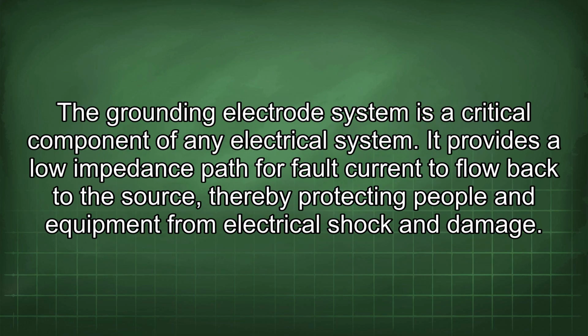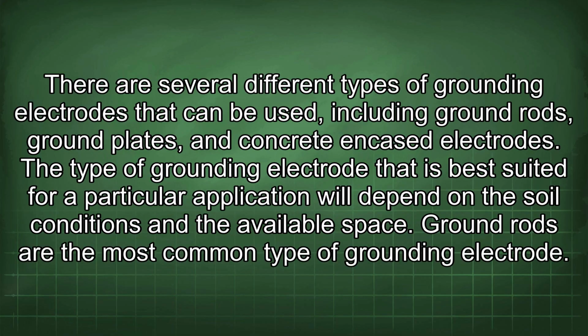The grounding electrode system is a critical component of any electrical system. It provides a low impedance path for fault current to flow back to the source, thereby protecting people and equipment from electrical shock and damage. There are several different types of grounding electrodes that can be used, including ground rods, ground plates, and concrete encased electrodes. The type of grounding electrode that is best suited for a particular application will depend on the soil conditions and the available space.